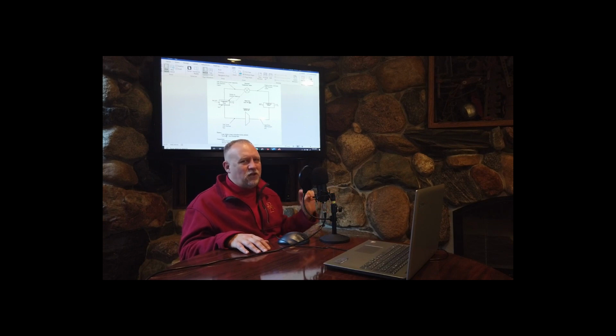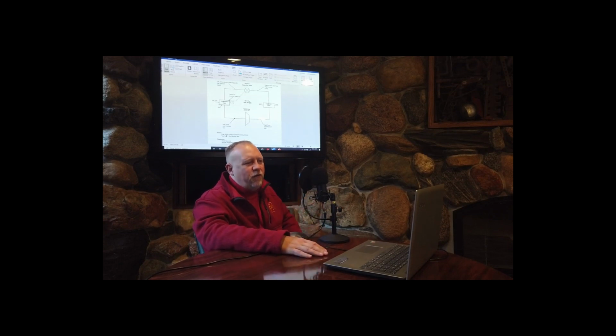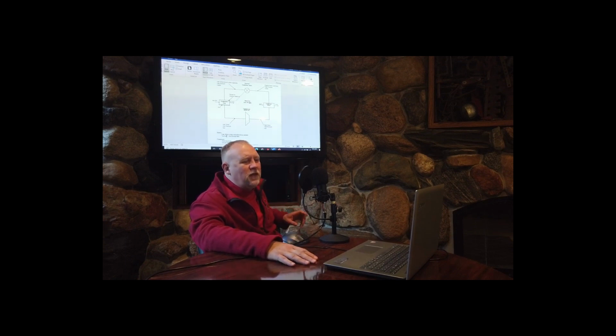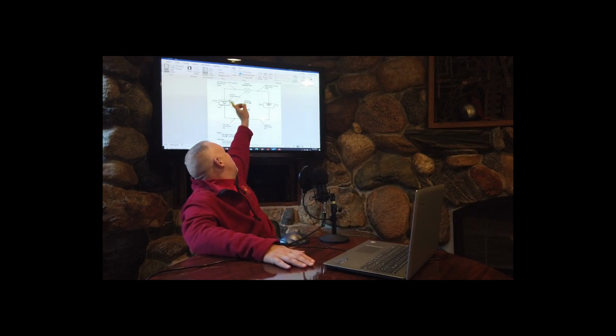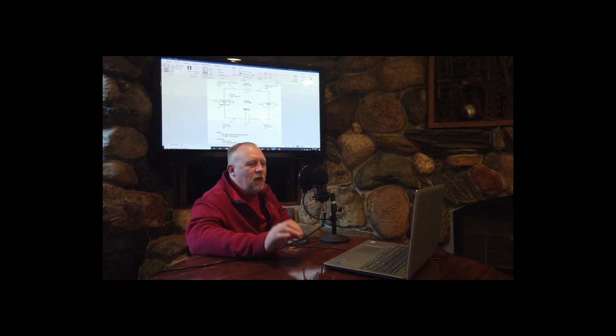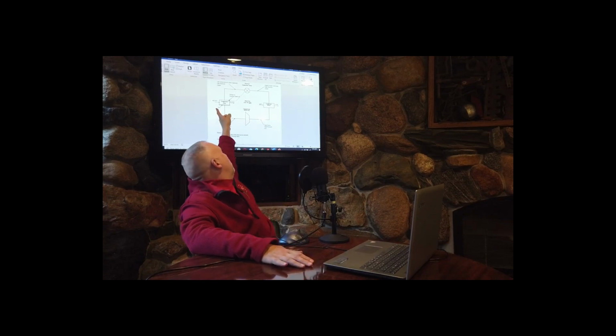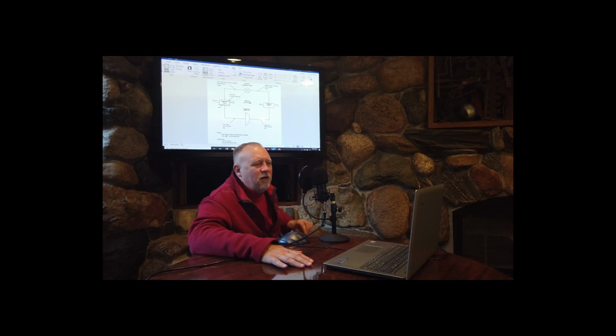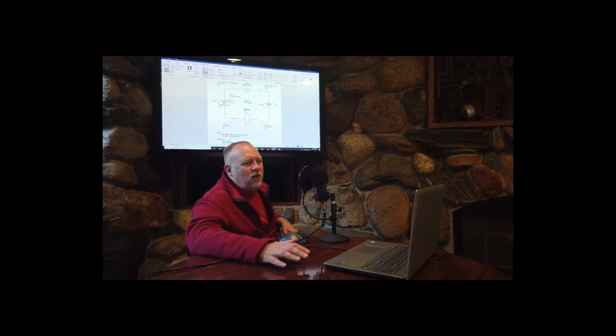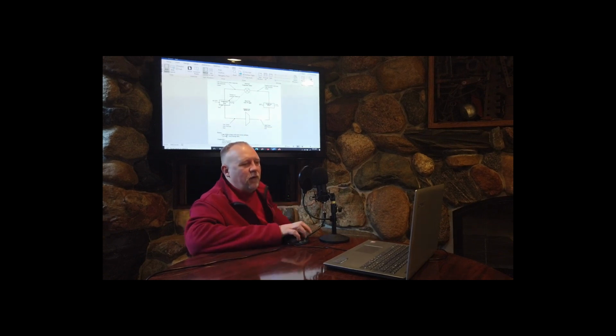The evaporator is a heat exchanger, so it blows return air over that coil, exchanges energy with the refrigerant. It boils that refrigerant, or rather, the refrigerant evaporates. The air gets colder. The refrigerant gains energy. It is now a low pressure and low temperature gas, but still has a higher energy state than up there. Not only does that return air lose temperature, loses sensible energy, it also loses latent energy in the form of moisture that condenses on the outside of the evaporator coil. That coil, as it drips, we have a drain pan that directs that water away.